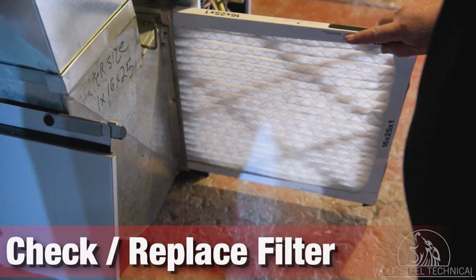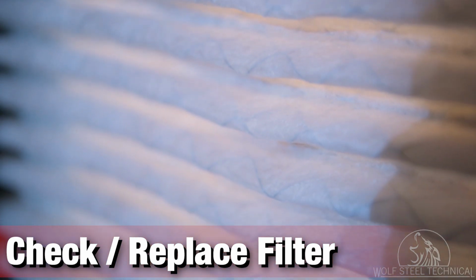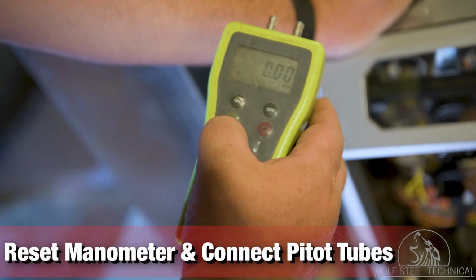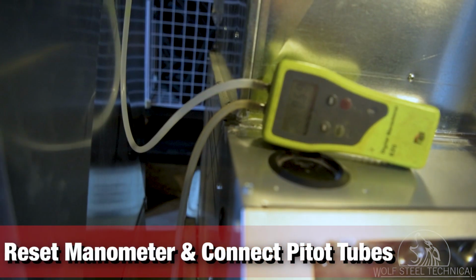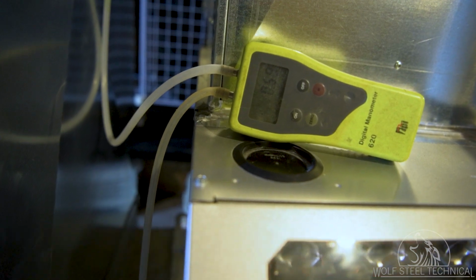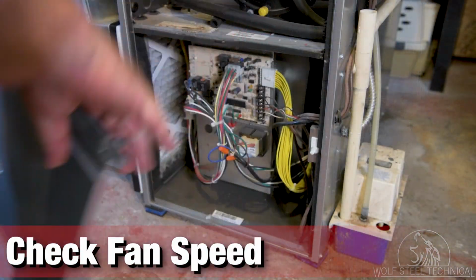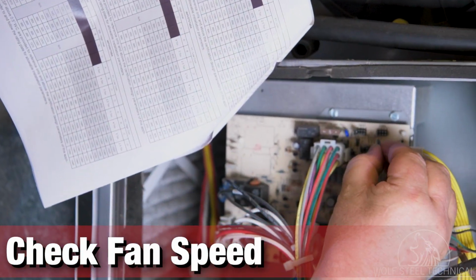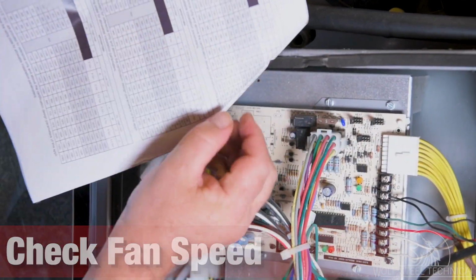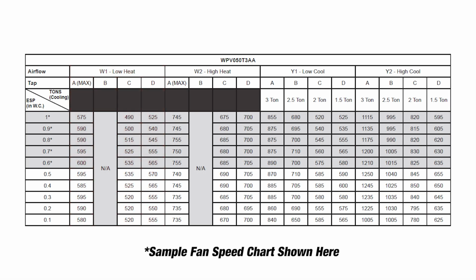Next, check the air filter to ensure it is free of obstructions, and replace it if needed. Reset your manometer so it reads 0 inches water column, and connect it to the Pitot tubes. Access the lower cabinet and check the fan speed using the fan speed chart in the product's manual. This is used to help determine which mode creates the highest fan speed.